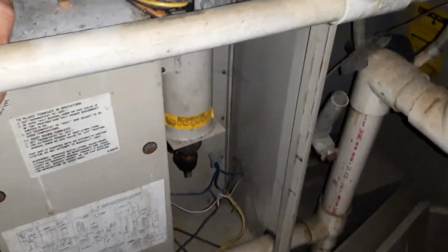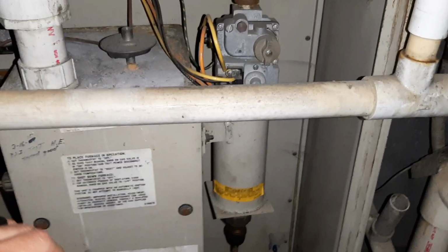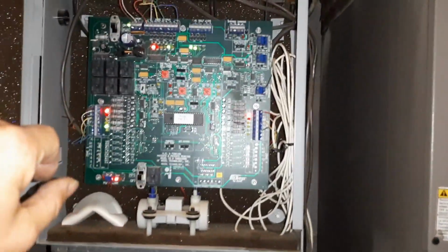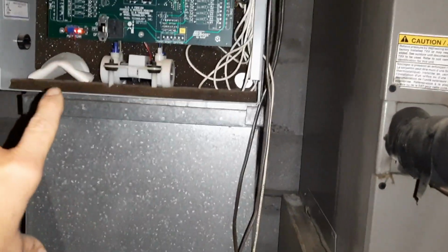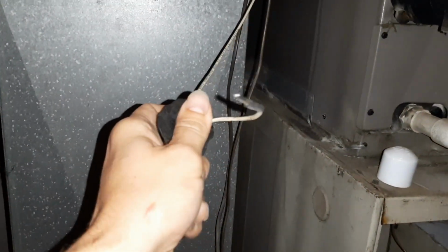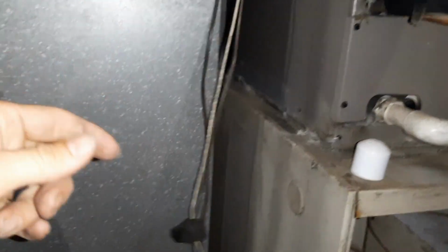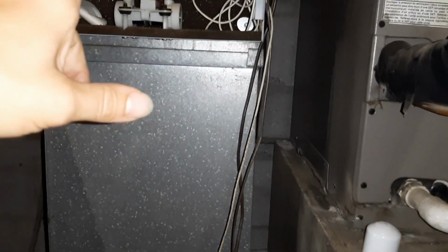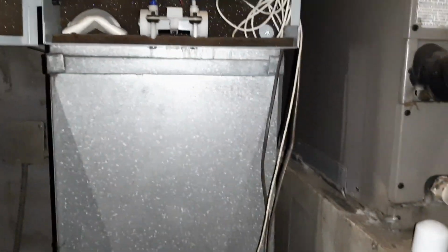I just kicked the heat on to try to get some load in the building, and both these things just fired off. So I do have LEDs on my control here. One thermostat was set to heat, one was set to cool. That may have been why they didn't have cooling. And my discharge air sensor's hanging, so that might have been why they didn't have cooling too.